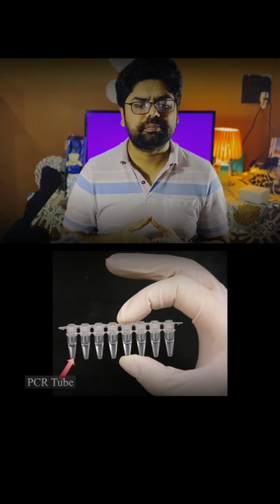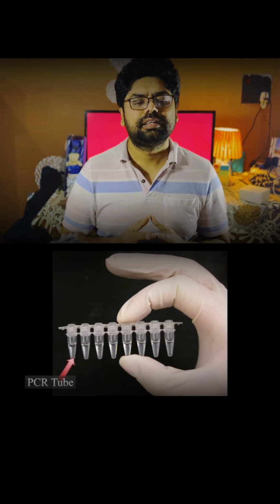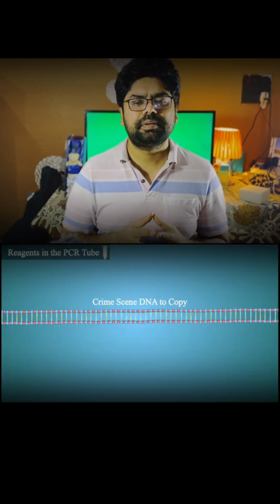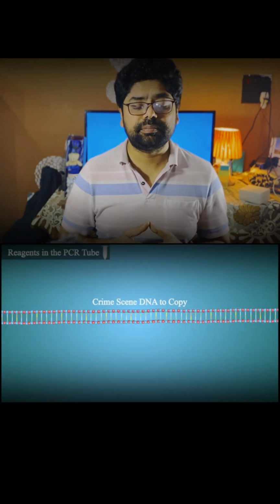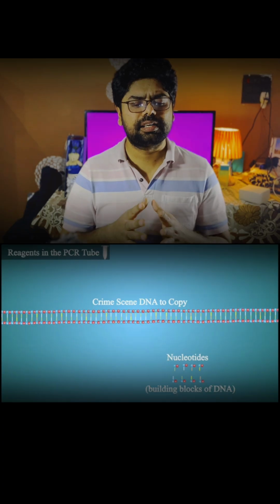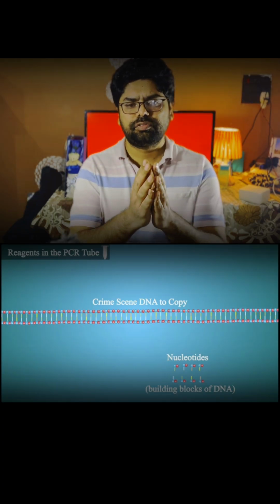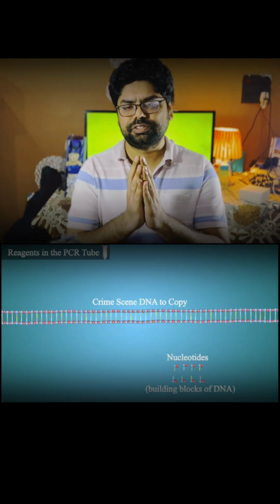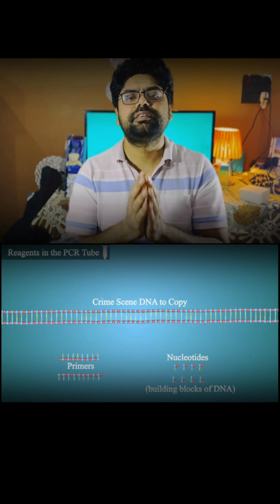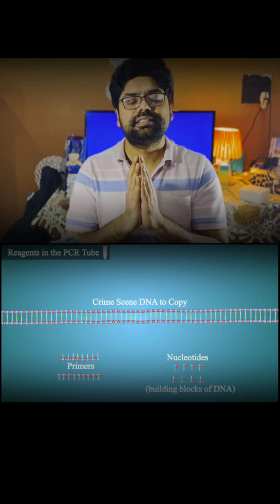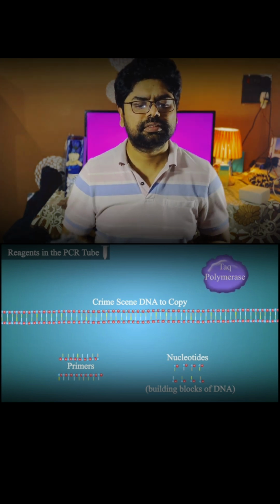So what is a thermocycler? The earliest thermocyclers were designed for use with the Klenow fragment of DNA polymerase I. Now modern PCR machines use Peltier elements. The lid temperature goes to about 105 degrees Celsius. And the thermal blocks mainly contain 48 or 96 wells. As you open the PCR machine, you will see it contains 48 or 96 well formats.